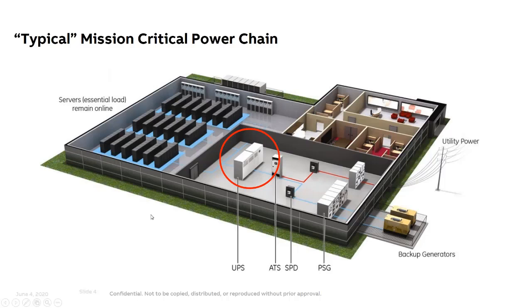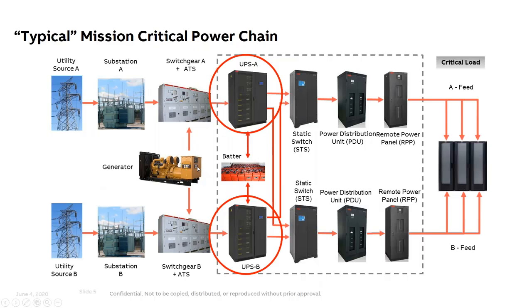So I've got two slides just illustrating where this UPS fits in. Typically you've got utility power, and with a little bit more detail, this is what a typical data center could look like, with utility power or generator power as backup power into the data center, then the UPS sitting there cleaning everything up before the power is fed into the IT load, the critical load. This is just a slightly different way of seeing it, but again showing the UPS as the guard between power from the utility or the generator and what is fed down the power lines, down the distribution equipment, down to the critical load.